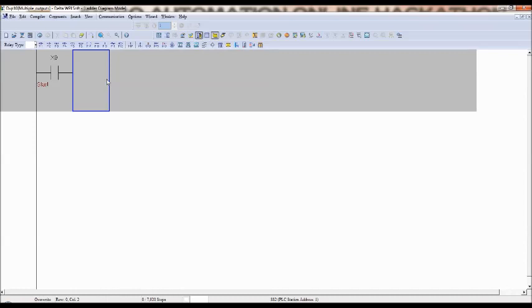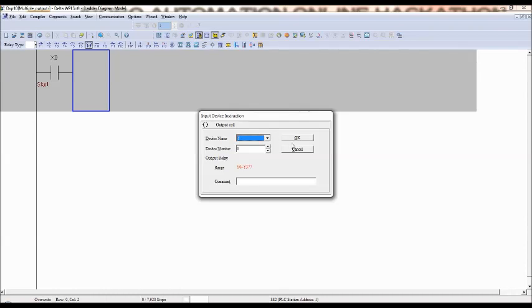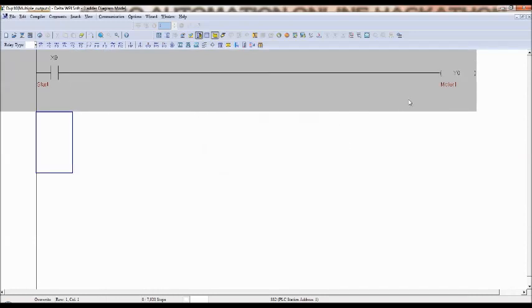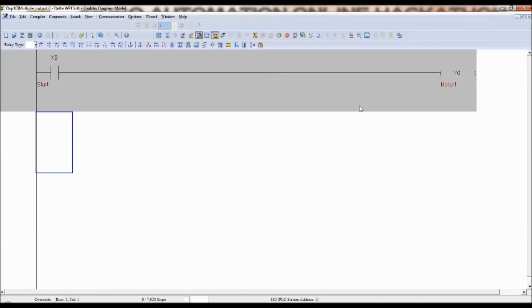So F7 is a coil, select F7 and then Y0 is the first output, say for example motor 1. But there is another motor that needs to be on when start button is operated. So in that case you don't have to take the second line, second network. In the same network you can add another output in parallel. Output cannot be used in series, output can be used in parallel.